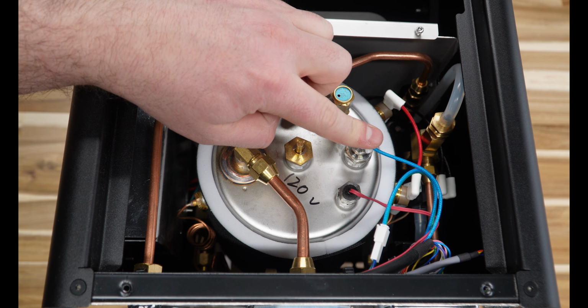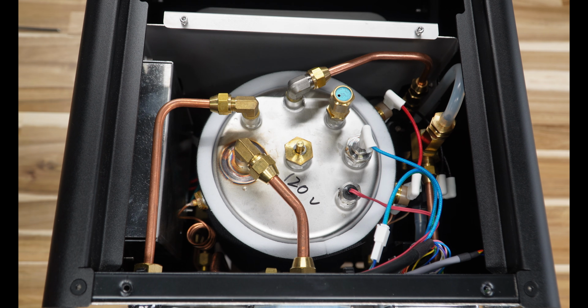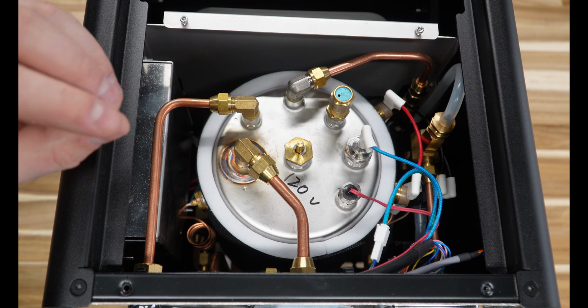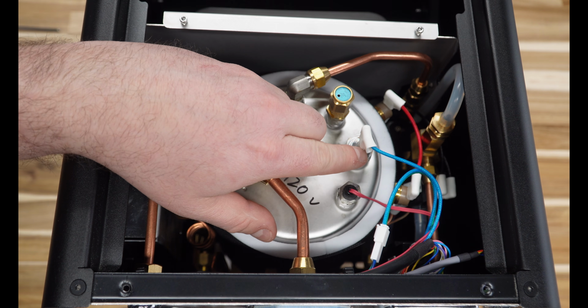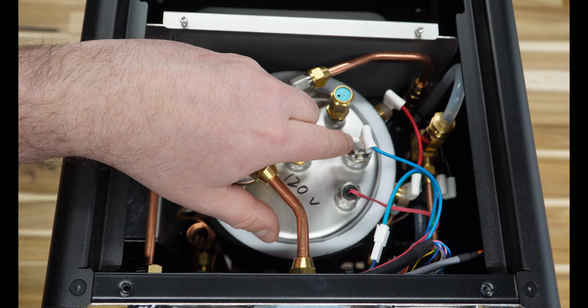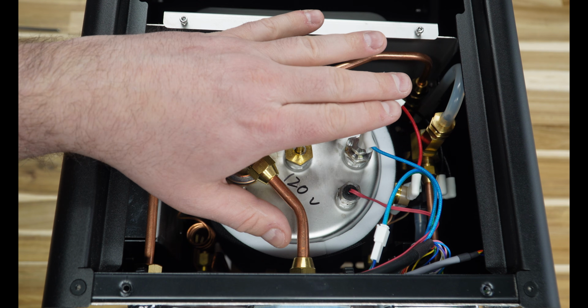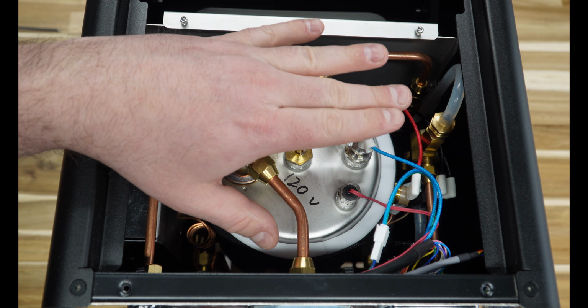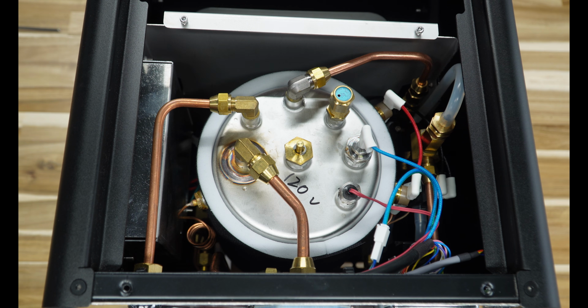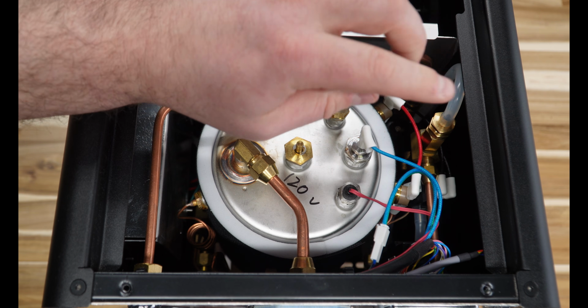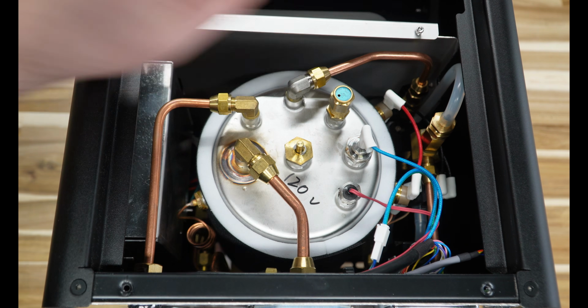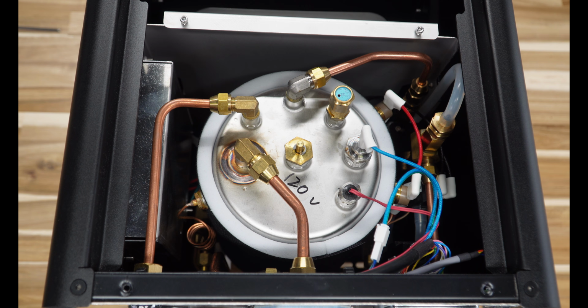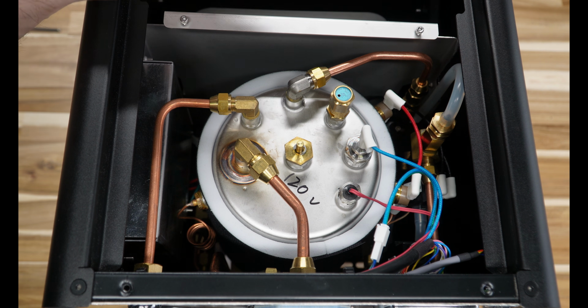Sometimes these will get dirty. You'll need to remove the probe and use some steel wool or something just to get all that sediment off. Another thing I like to point out is if you're using really purified water, like distilled, which you shouldn't do, people will say that my machine is acting weird. Usually one of the first things we ask is, are you using distilled water or really pure RO water? Because those types of waters don't conduct electricity. So probably not something you'll need to mess with a whole lot, but if your machine isn't filling for whatever reason, that's probably one of the first things I would check.